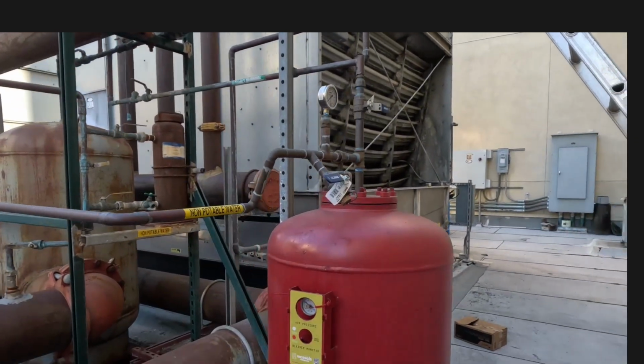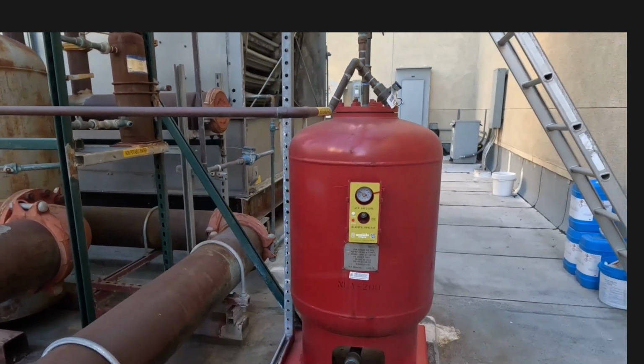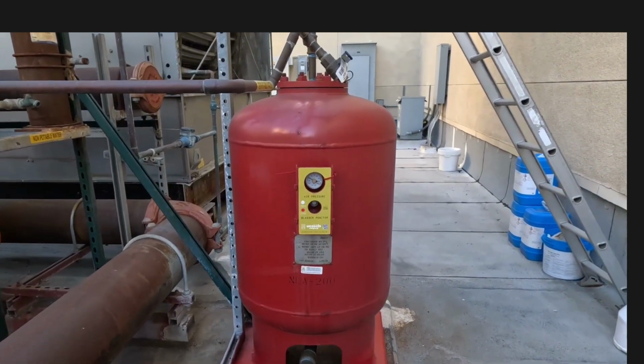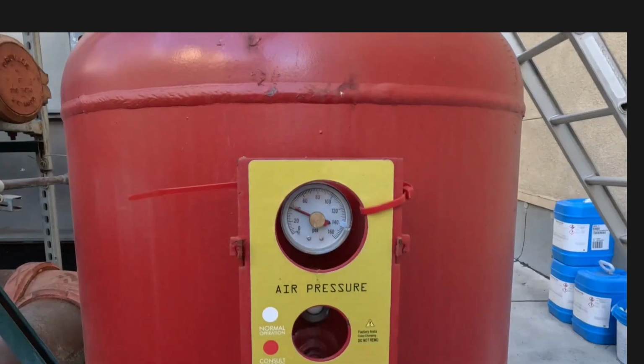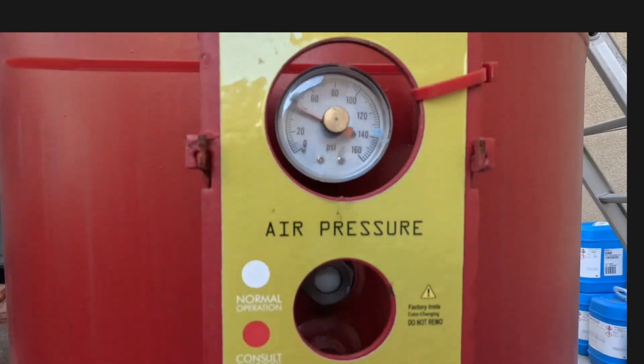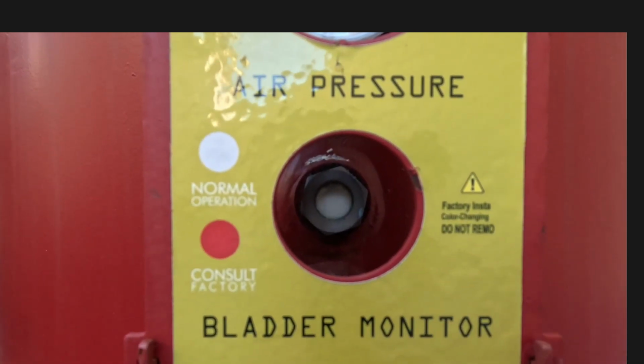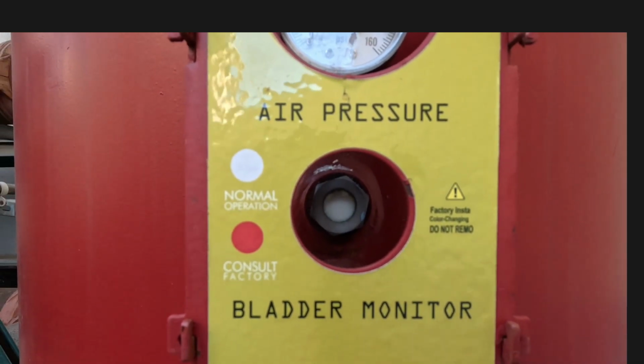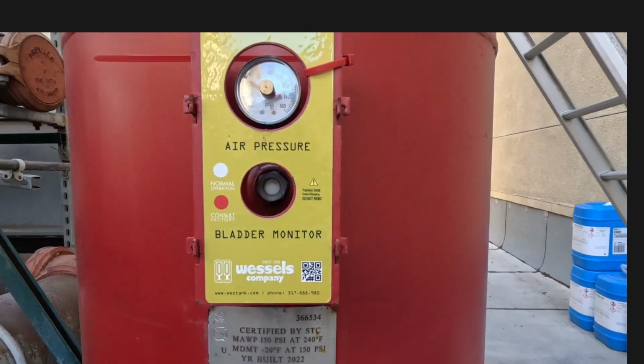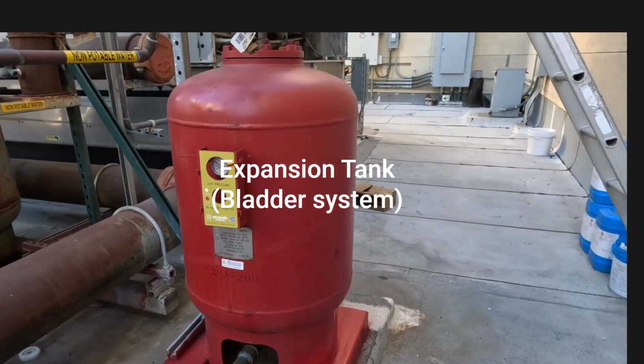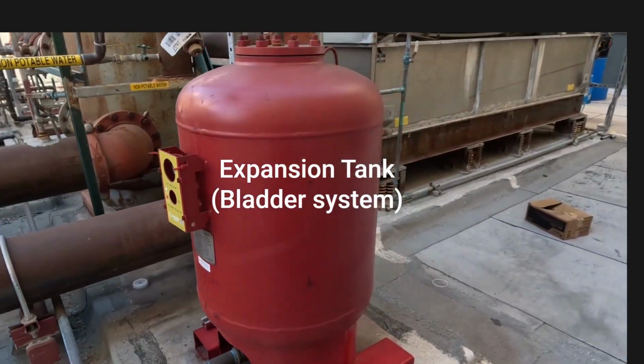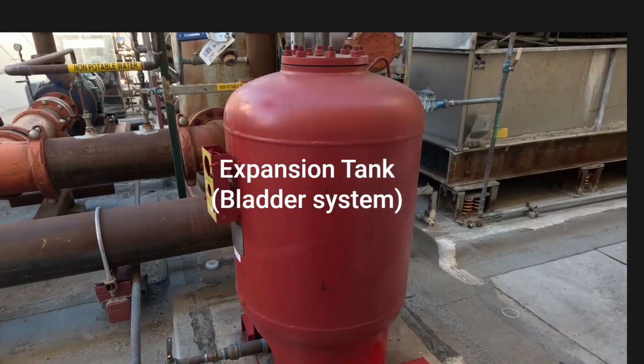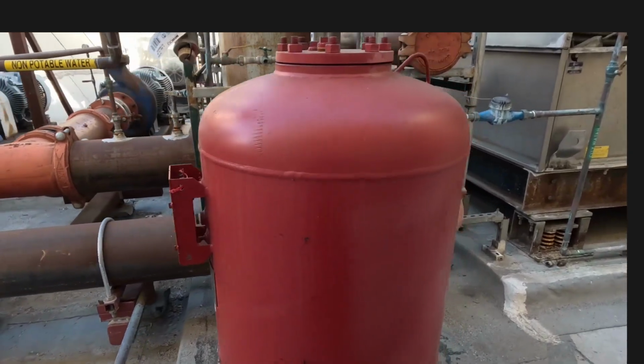This bad boy right here, this is your expansion tank for the system. And this expansion tank's pretty neat. It has a pressure gauge on it. And then you also have the sight glass telling you if the bladder has been compromised or not. So this type of expansion tank has a bladder inside of it, a rubber bladder that expands and contracts with the pressure of the system.